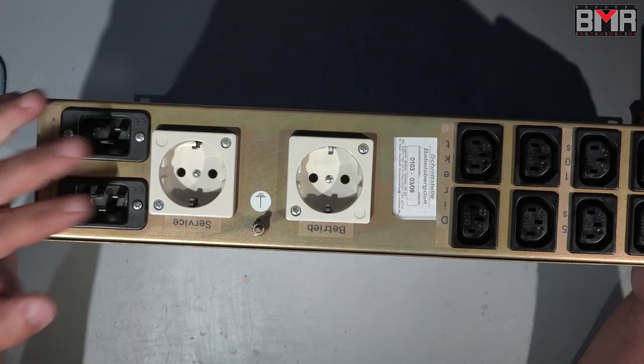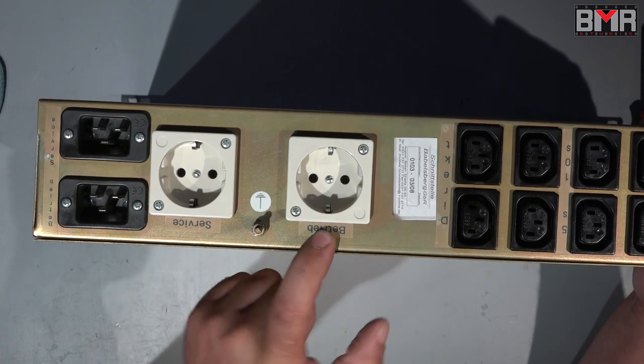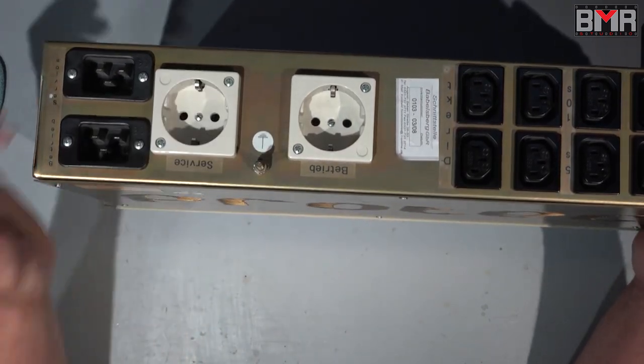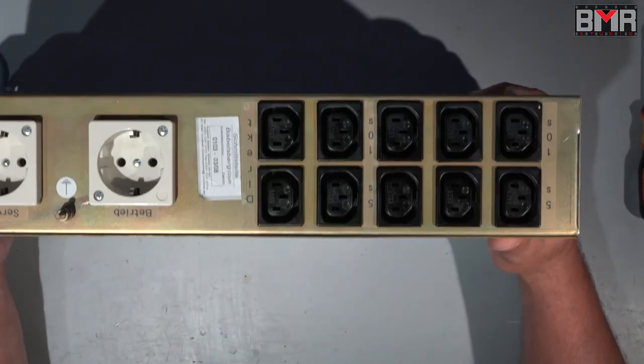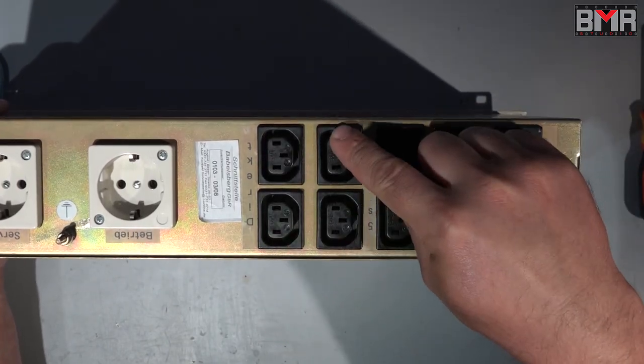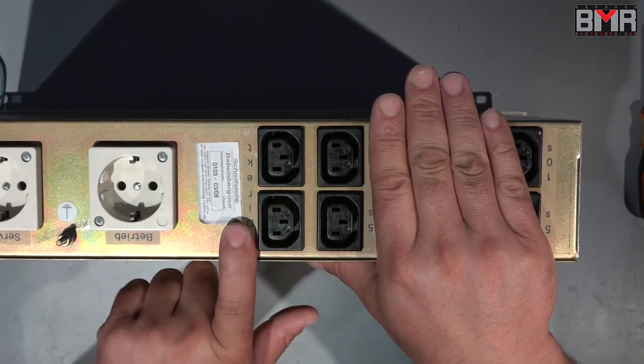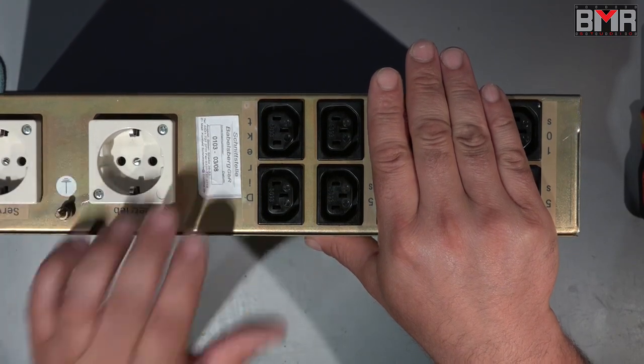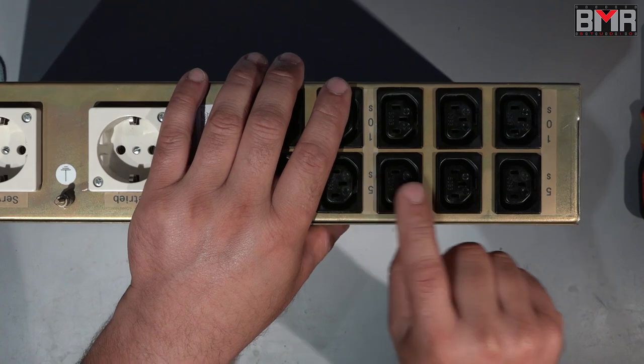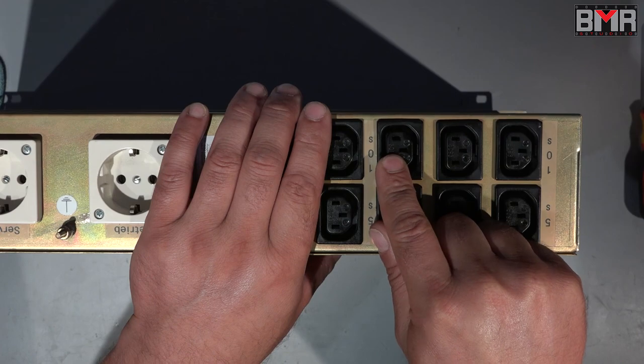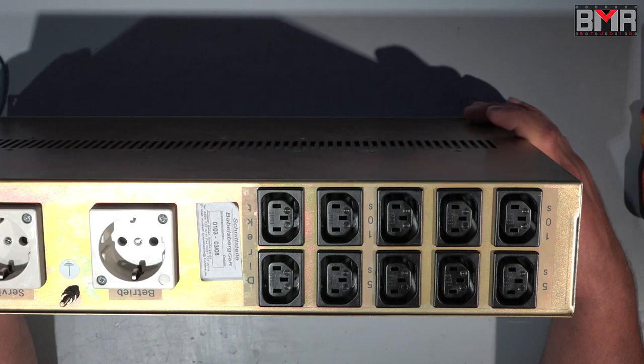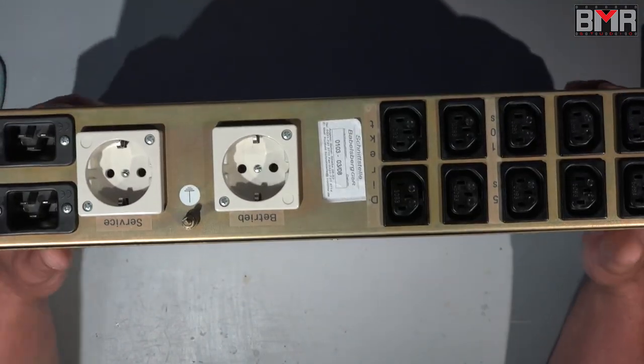We have two individual power inputs, here is one output, another output, really nice grounding point, and many IEC 13 outputs. This section, these 4, is a direct output. The next section, these 3 here, has a 5 second delay, and this one here, these 3, has a 10 second delay. Everything is just really old-fashioned, really German quality, absolutely built like a German tank.